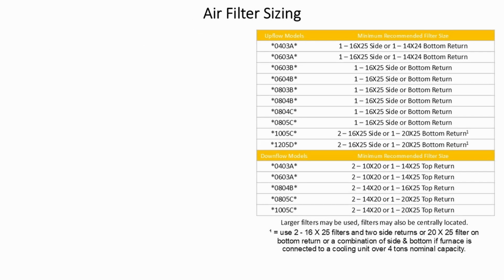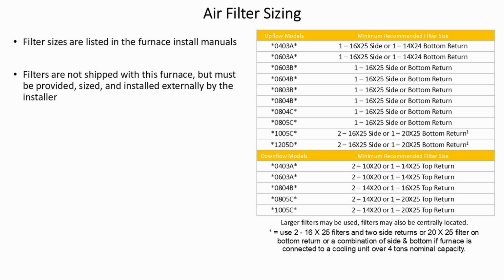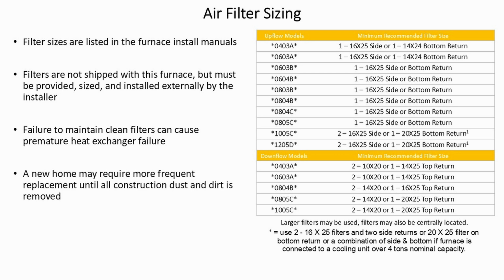Air filter sizing. Here is a chart showing the upflow and the downflow models of furnaces and the minimum recommended filter size for each. Filter sizes are listed in the furnace installation manual. Filters are not shipped with the furnaces, but must be provided, sized, and installed externally by the installer. Failure to maintain clean filters can cause premature heat exchanger failure. A new home may require more frequent replacement until all construction dust and dirt is removed.